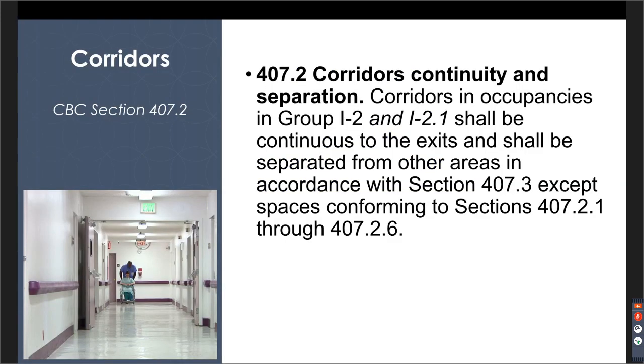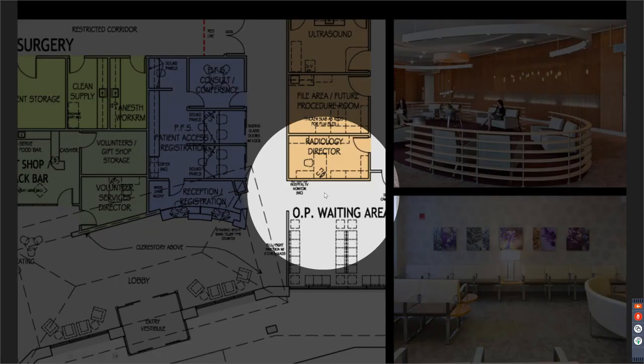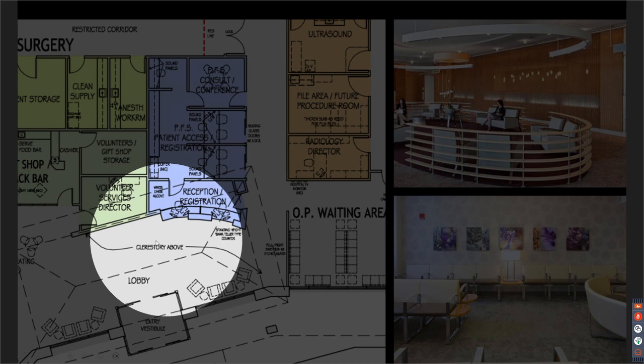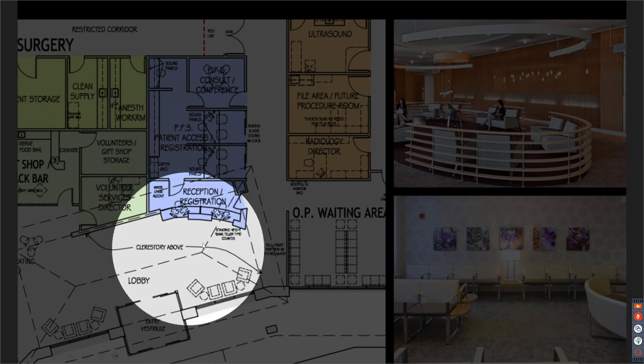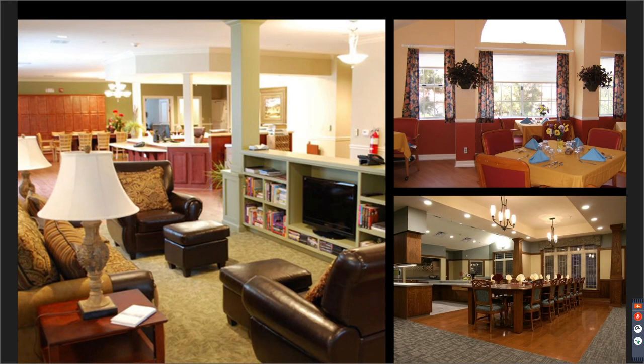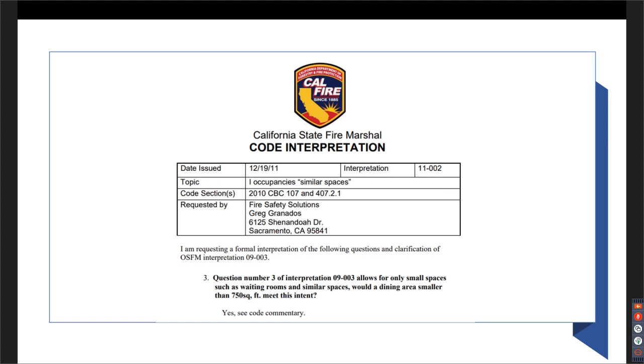The reception area here, registration area, that gives the direct supervision of that space that's open to the corridor. And in this case, you've got the lobby area and you've got a waiting area. What about these similar areas? What are those? That's part of trying to have these facilities become a little bit more social, more like a home environment. So areas like that dining up top right, could that be open to the corridor? Yes, that could be considered a similar area under certain circumstances. The cooking equipment's not going to be in there, but tables and chairs, sure. Under a certain size, sure. It helps people come out into these open areas. There's a State Fire Marshal code interpretation that discusses that a little bit further.